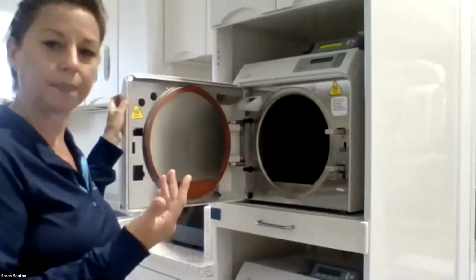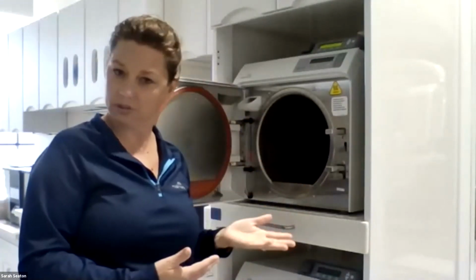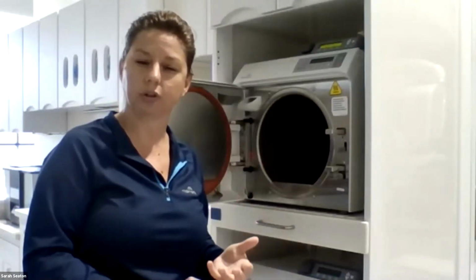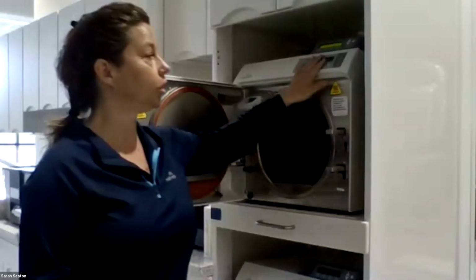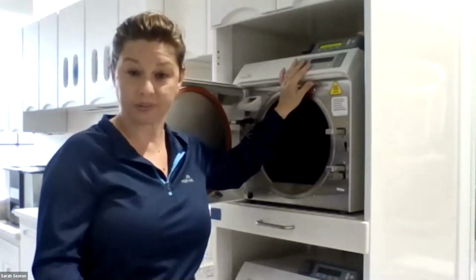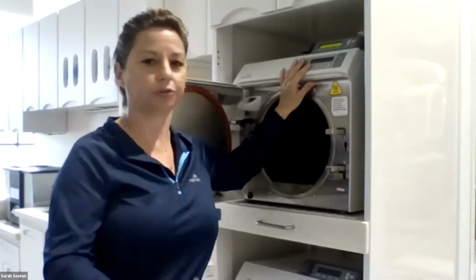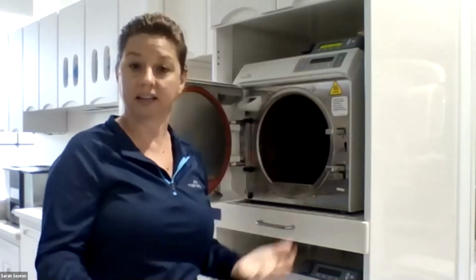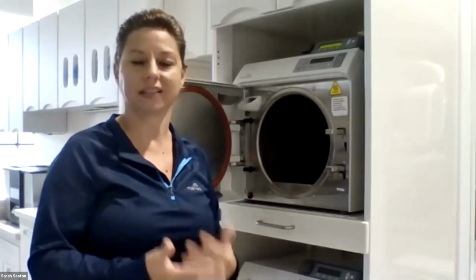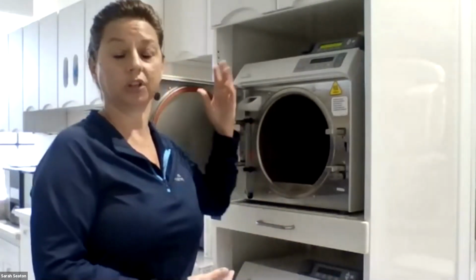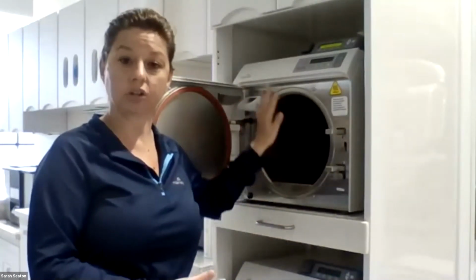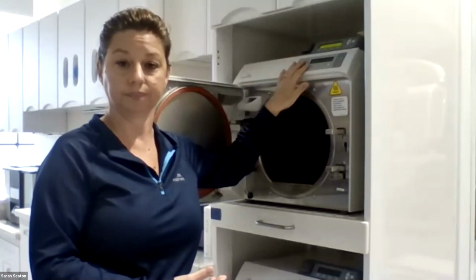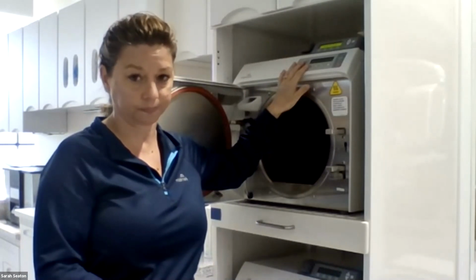Then you'll want to, of course, open it up again, drain your reservoir, put new clean distilled water in it, and then you want to rinse that cleaning agent out of all of your internal valves. So again, you'll close the door and you'll press an unwrap cycle. It's a little bit shorter cycle just to flush that all through the system. And then again, once that cycle gets to the drying portion, then you'll want to press stop, save some time, and then drain it again. Once you've done that, you can fill it with clean distilled water, and then you're good to go for the next cycle. You're not finished with the monthly maintenance, however.